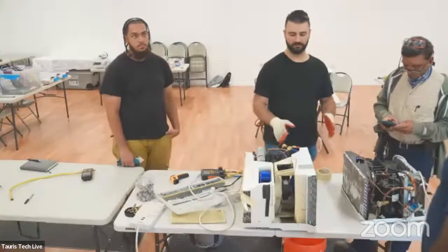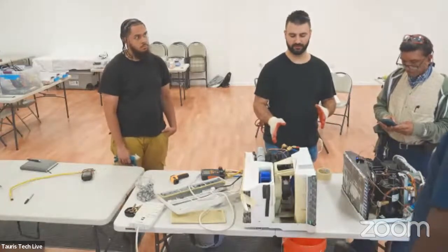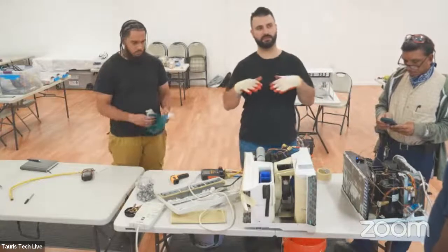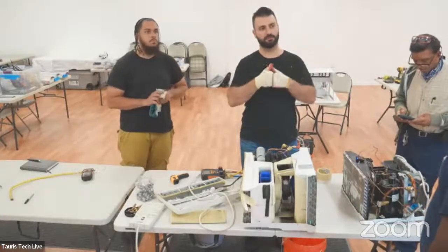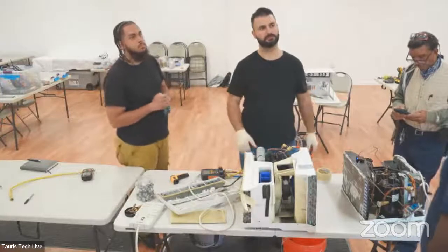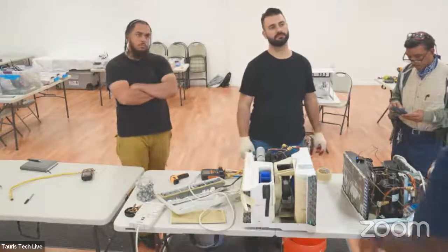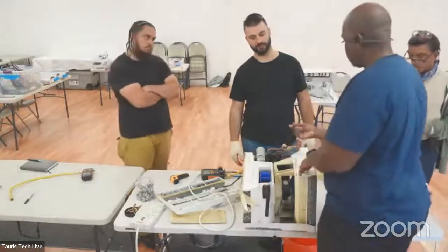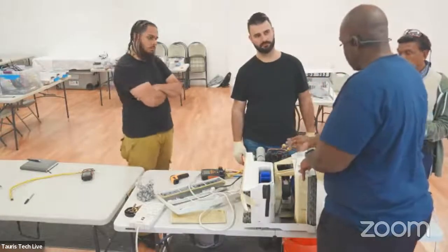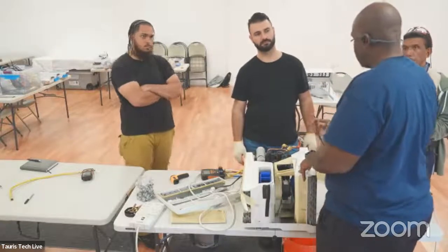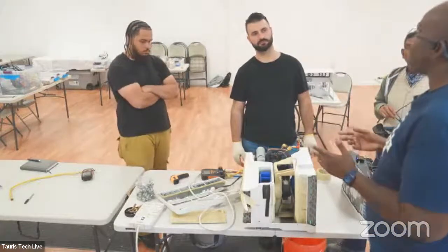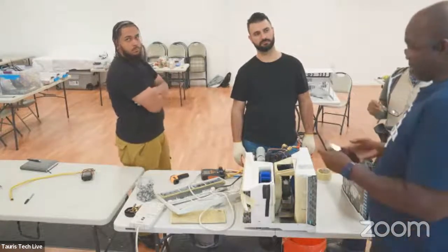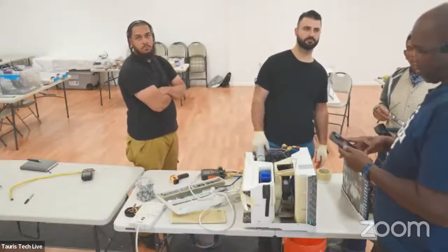So let's say we're changing our R22 in a house, not too big of a unit. You said we need to flush it. If you are doing what's called a retrofit, it's not so much the refrigerant, it's also the oil. You can look here, you see you have oil, because when we were pulling out, oil was coming out. So it's really the oil.